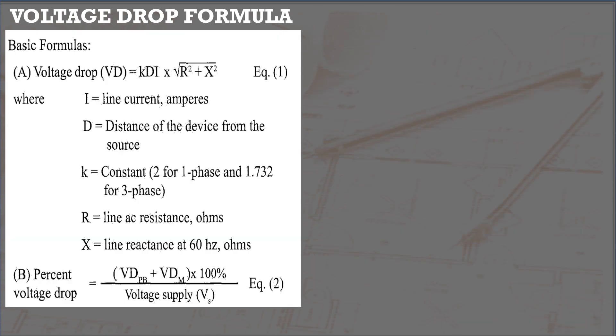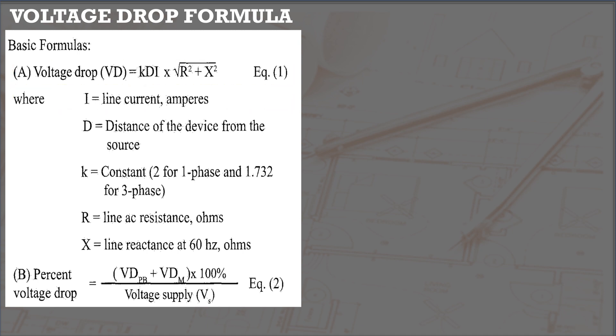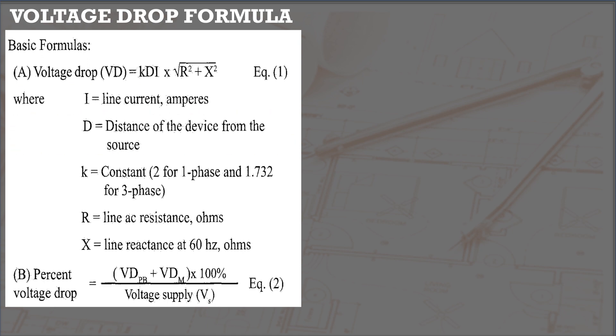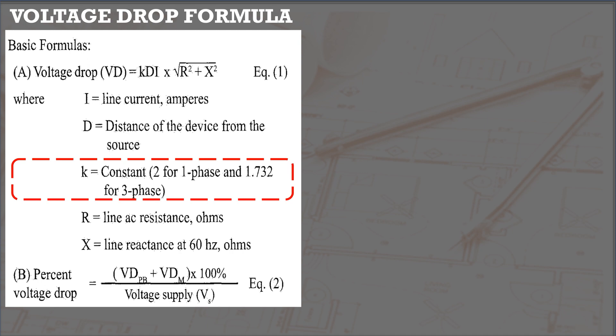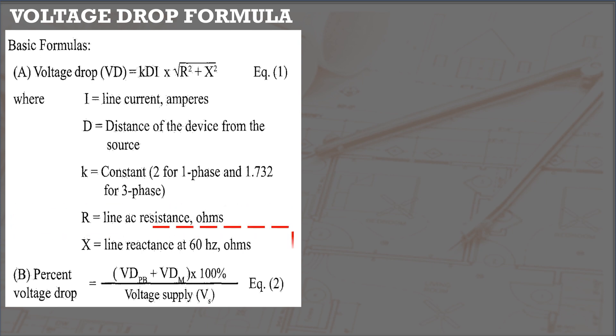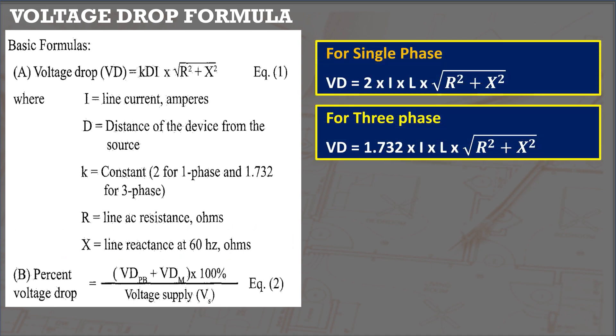This voltage drop formula was taken from Appendix D, wiring design examples, D15 — Voltage Drop Calculation. Where I is the line current in amperes, D is the distance of the device from the source in meters, K is constant (2 for single phase, 1.732 for three phase), R is the line AC resistance in ohms per 305 meters, and X is the line reactance at 60 Hz in ohms. These are the voltage drop formulas for single phase and three phase.